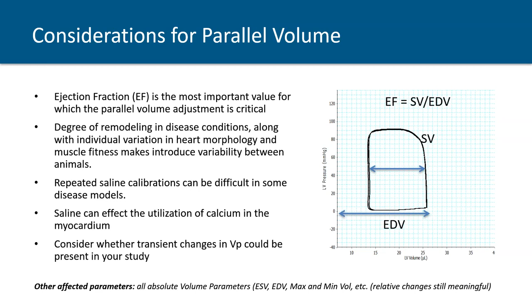I would like to point out at this point, unlike taking multiple samples or measurements of a reference measure for stroke volume, doing repeated saline calibrations can be quite challenging, particularly as saline affects calcium cycling in the heart and is a pretty profound myocardial depressant. If you're looking at models where the animals are in heart failure and you've spent 2 months trying to develop this model, you may want to assess maybe just doing 1, at the most 2 measurements, or perhaps even not more than 1, because you could actually kill animals if the technique is not done right, if you've injected too much saline. So in some cases, you may not always be able to get repeated measurements of the parallel conductance, and typically, even in healthy animals, you probably can't get more than 3 measurements at a time that you can average.